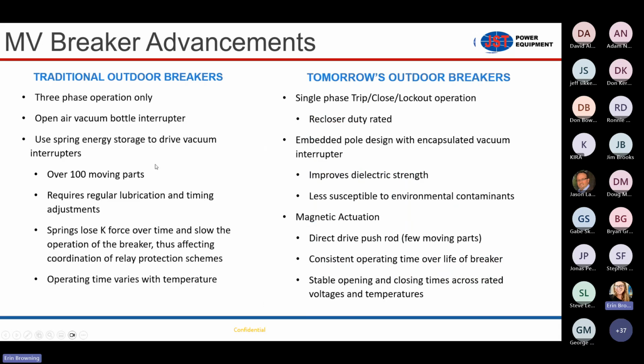So traditional outdoor breakers, and again, we're talking 15 kV to 38 kV substation class outdoor freestanding circuit breakers. Traditionally, these breakers have been three-phase operation only for as long as they've been around. And that's probably because of the design approach for the operating mechanism, taking into account some size constraints, what was realistic when pen and paper first created a circuit breaker. It resulted in a single operating mech driving three poles simultaneously, and as a result, you get a three-phase operation breaker.